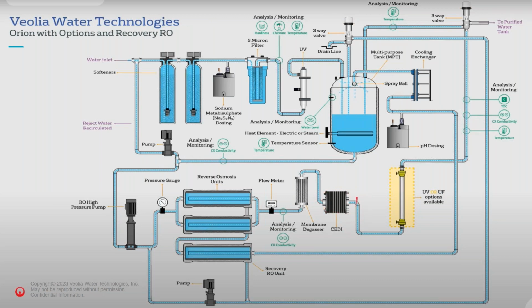at the end of the system here. So at this point, after the CEDI, we're essentially producing purified water. And this system has been designed, as you may remember at the beginning, I said we tend to over purify on the generation system. So we're looking at conductivity probably around less than 0.2 microsiemens. In terms of microbial count, it will definitely be less than 50 CFU per ml, probably nearer 20 to 30, in some cases even less than that, depending on the site and the system. In terms of TOC, again, it will be less than 50, and in real cases maybe even 15 to 20 in terms of TOC. So we're really getting into low levels here.